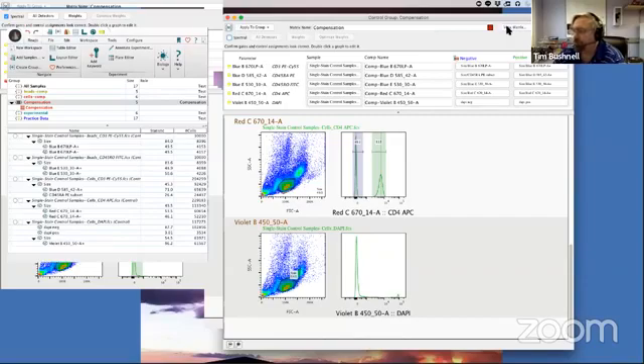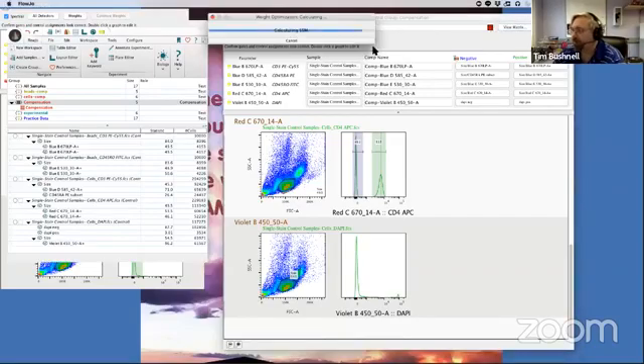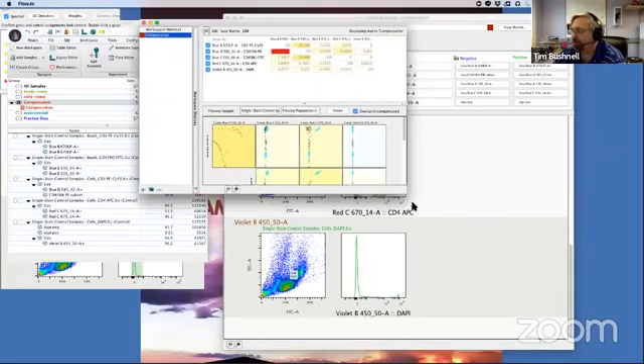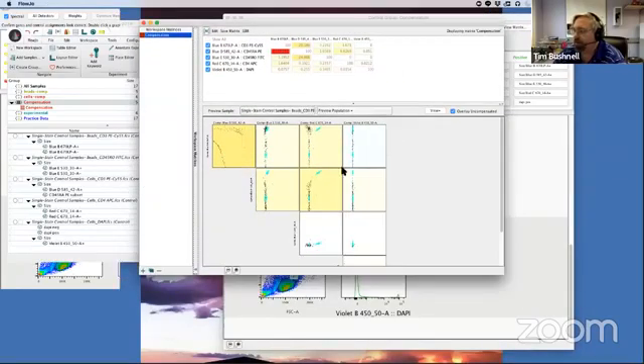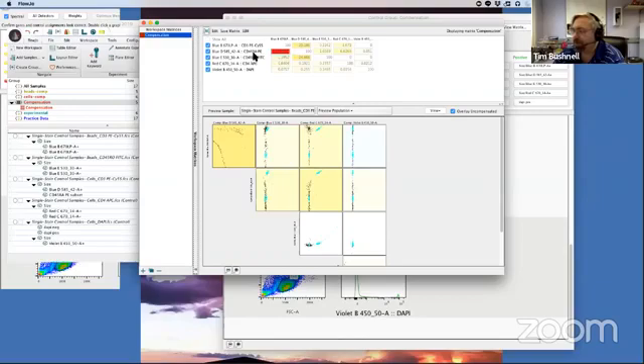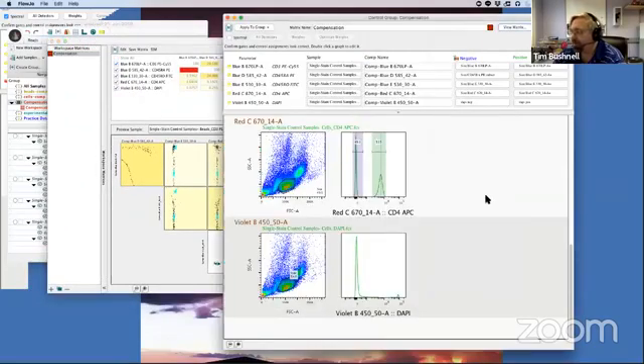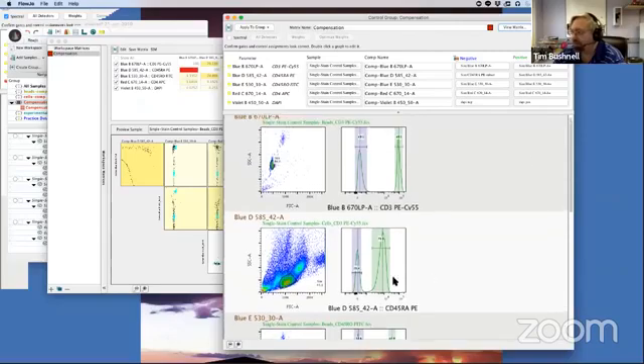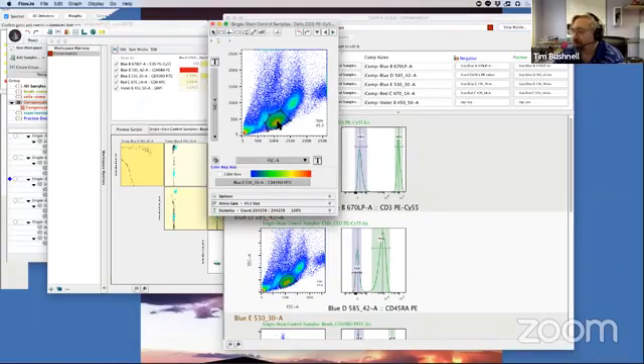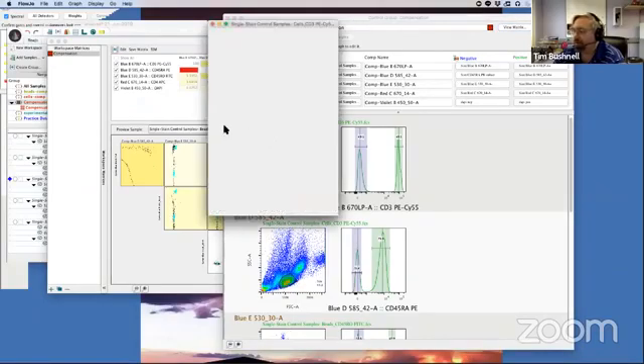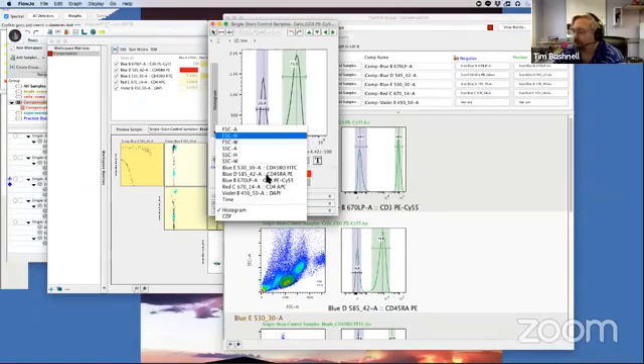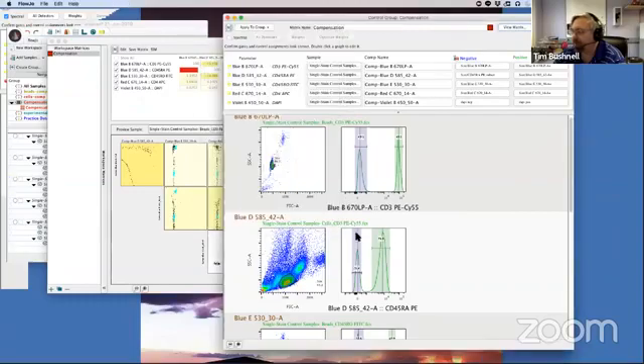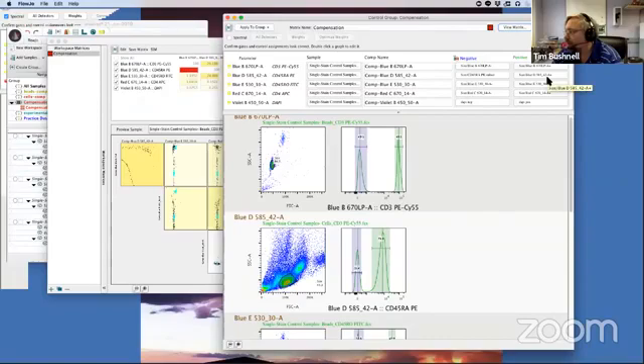So if there's a little bit, if the compensation isn't 100% perfect, because this is at the far edge of our detector, we'll be okay. So here we go. We're going to put our DAPI negative, DAPI positive. So now you can see we've got a green light for everything. Now we're going to view the matrix. So when I view the matrix, it's going to calculate the matrix and it's going to show us here. So we can see what our matrix is. And you can see here, there's definitely a problem somewhere. So we're going to have to go take a look at that. The CD45RA spilling over 400%. There's clearly a problem. So we're going to have to go take a look at that population again. So that is this population here.